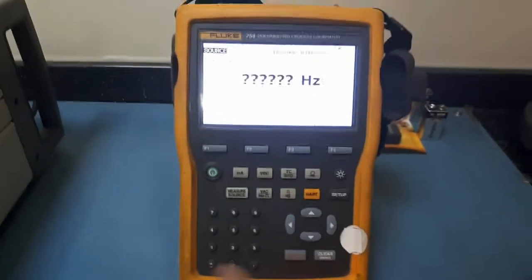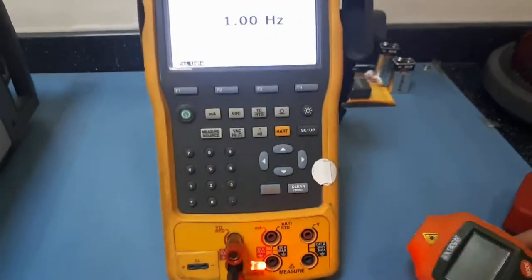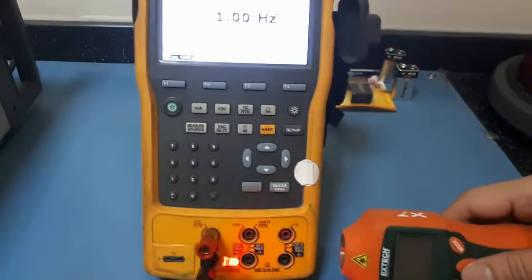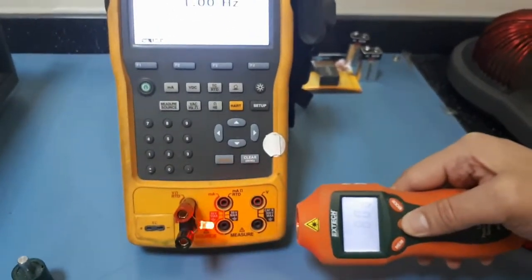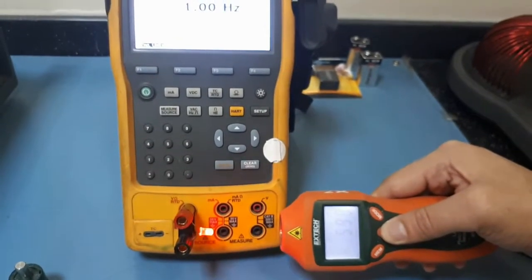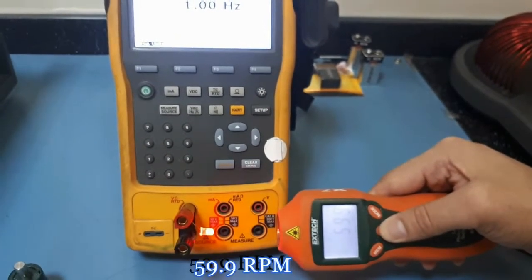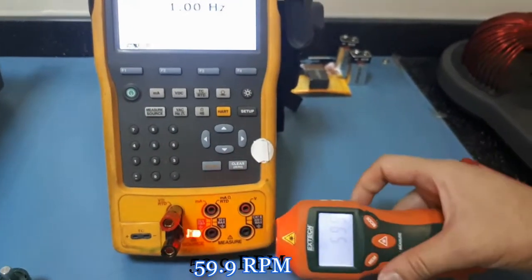And we will start at frequency. 1 hertz is equal to 60 rpm. So we will check 1 hertz. Enter. It's blinking. And compare. Expected, it's 60 rpm. Check. There. It's 59.9 rpm. It's good.